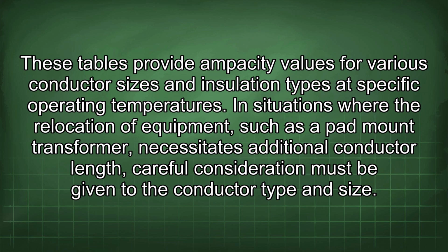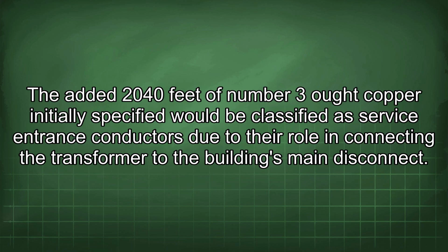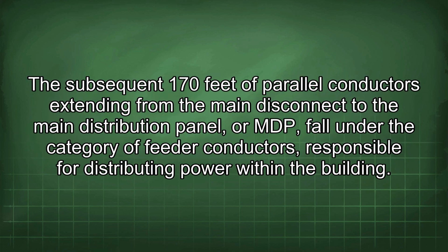In situations where the relocation of equipment, such as a pad mount transformer, necessitates additional conductor length, careful consideration must be given to the conductor type and size. The added 20-40 feet of number 3/0 copper, initially specified, would be classified as service entrance conductors due to their role in connecting the transformer to the building's main disconnect. The subsequent 170 feet of parallel conductors extending from the main disconnect to the main distribution panel, or MDP, fall under the category of feeder conductors responsible for distributing power within the building.